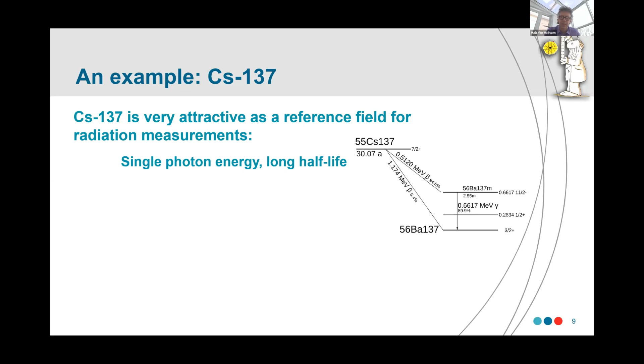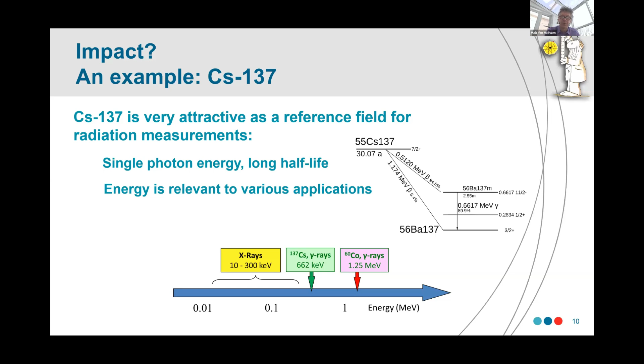So let's give an example of a source, and you'll see why we're coming to cesium-137. It's very attractive as a reference field for radiation measurement. It has a single photon energy and a long half-life. So sort of 30 years, and it decays by beta and gives you a single gamma of about 662 kilo electron volts. And that's really nice because it sits in the middle of our energy range of interest. If we sort of think about X-rays from about 10 keV up to sort of 300, cobalt-60 is our upper end around 1.25, and cesium sits in the middle. And it's got this combination of a good energy, long half-life, and a single photon energy. It's not a complex spectrum, so that makes it a very, very nice reference field. And it's available also, key component, available at a suitable activity level.